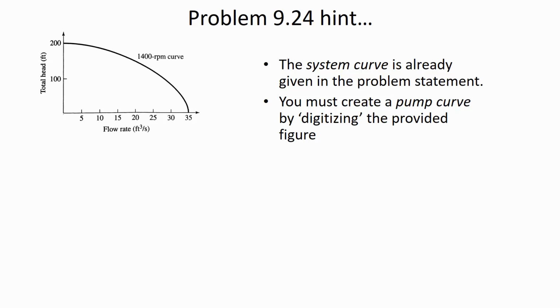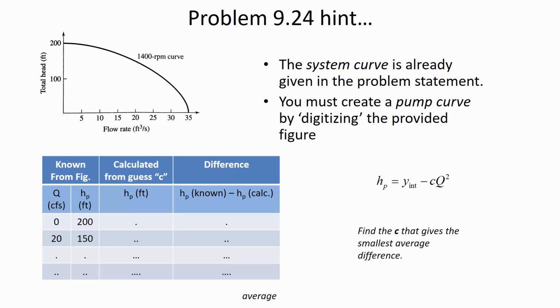All right, so on this problem, problem 9.24, they give you the system curve, but they give you a figure of the pump curve. And what you'll need to do is digitize that. What I mean by digitize is take some points off of the graph, and you will need to figure out what the intercept is, and then some coefficient like a C value, so that you can set the two curves equal to each other. So in other words, it's kind of like a regression in a sense. You're going to have the system curve, but you need to come up with a pump curve before you can solve the problem. There's also a couple of other hints for other problems on the handout.